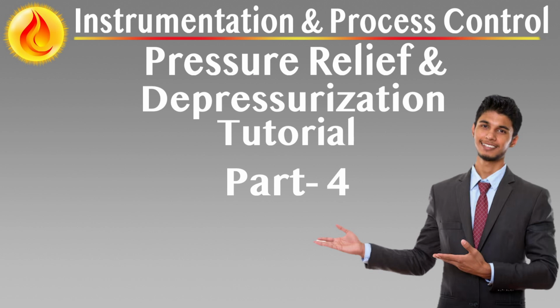Instrumentation and device selection. Key factors to consider when selecting flow meters for flare service include high turndown ratio to capture both low purge flows and high rate emergency events, non-intrusive or low obstruction designs to prevent pressure drop or risk of blockage in a critical safety system, suitability for varying gas compositions, temperature ranges, and possible two-phase conditions during depressuring, and robustness for long-term operation in challenging service environments, including potential fouling or corrosion.